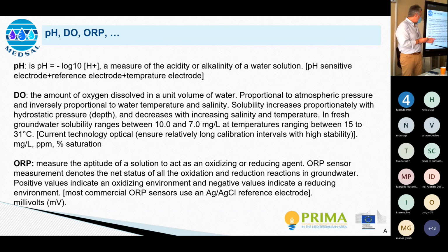It's too long. And last but not least, you have the ORP, the oxidation reduction potential electrode, which measures the overall aptitude of a solution to act as an oxidizing or a reducing agent. What you have here is a measurement that gives you the net oxidation or reduction status of your water solution. And this is a result of all the kinds of reactions you have in your water solution. These reactions can be seriously affected when you have salinization phenomena.